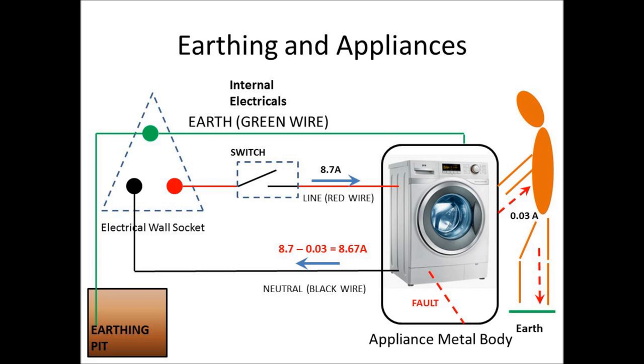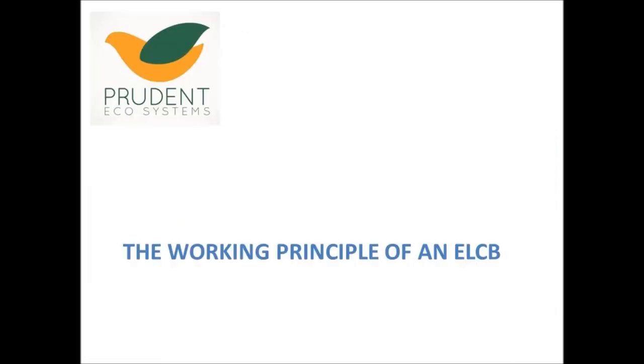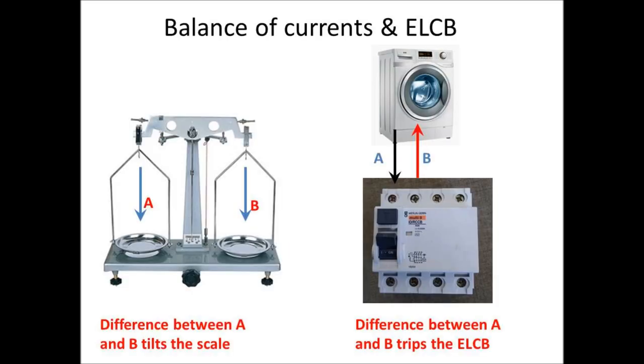The reason is that if there is a difference in current between line and neutral, then it is likely that a person is getting a shock, and hence tripping the circuit is necessary for safety. The ELCB is designed to trip at a leakage value of 30 milliamps or 0.03 amperes, because beyond this it can be dangerous for humans. It is important to note that the ELCB is not checking the absolute value of current in the line — that is 8.7 amps in this example — hence quite often even a very low power appliance having a leakage could cause an ELCB to trip the power to the entire house. The working of an ELCB is easier understood with the analogy of a precision physical balance.